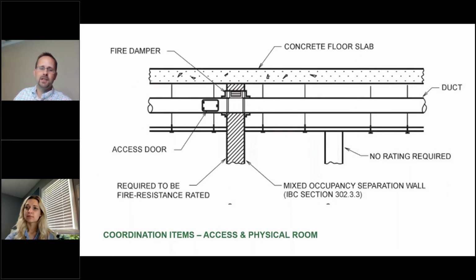And then in general, with these there is coordination for access. These have to be accessed very regularly, especially in healthcare environments. So in every fire damper or fire smoke damper, there's going to have to be an access door, and that access door needs to be accessible. It needs to be the proper size, at least 10 by 10. If a duct is smaller than 10 by 10, it needs to have a removable section of the duct, like if you have a 6 or 8 inch round going through a wall with a fire damper.